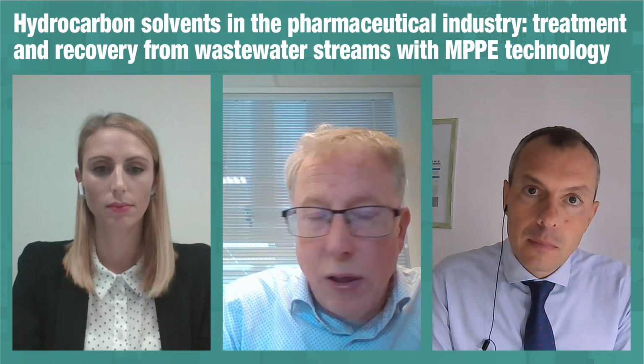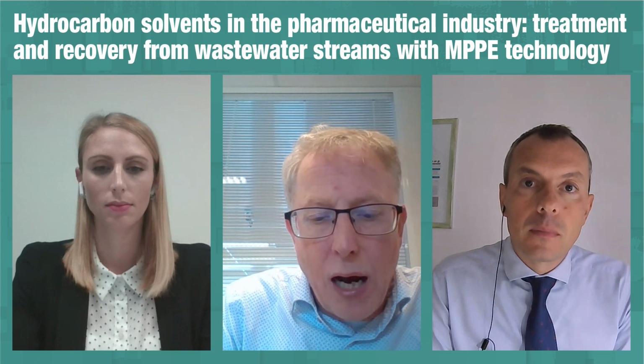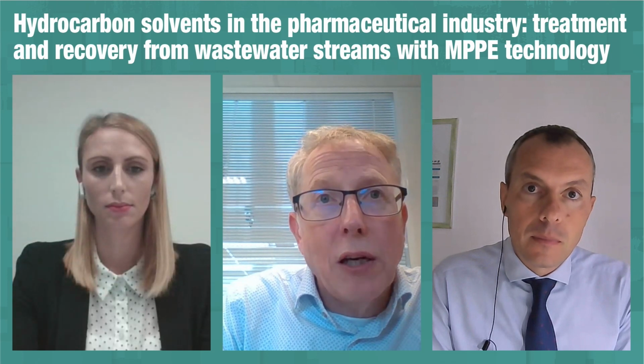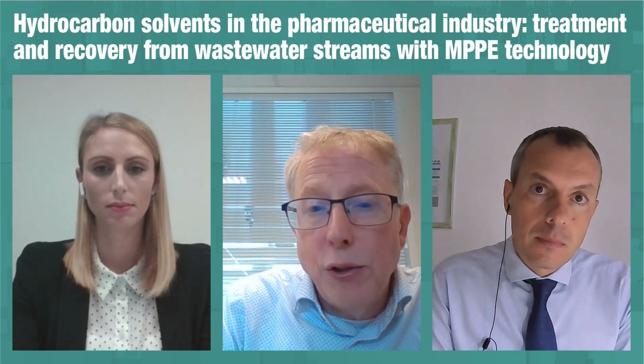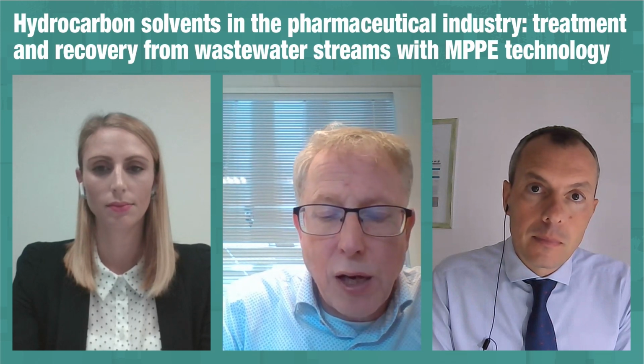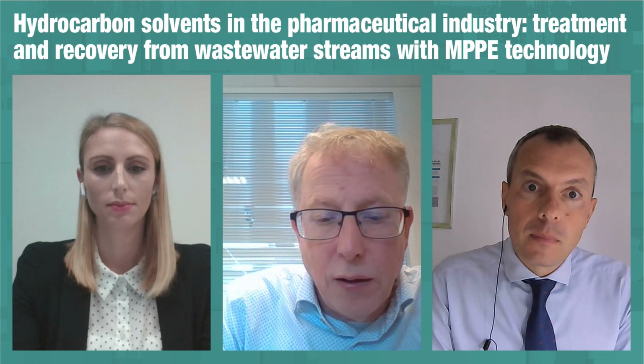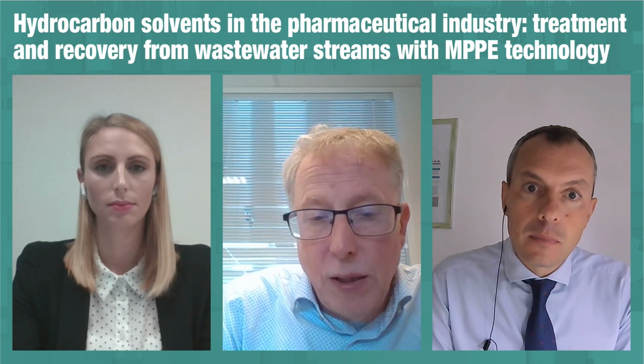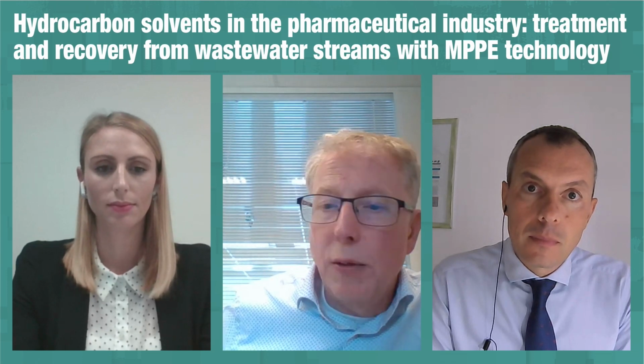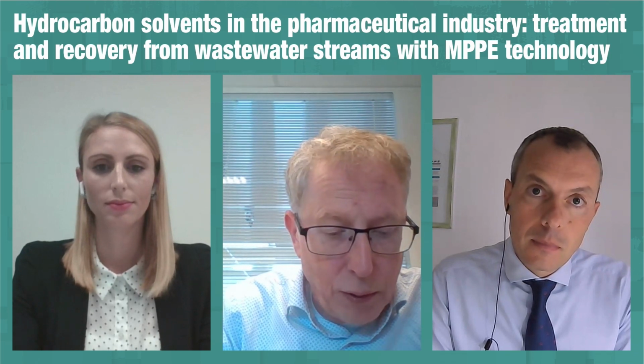And once the media's lifetime has ended, then we take it back and we either dispose of it in an appropriate way, or in some cases, in cases of clean applications, we actually can rejuvenate the media. So we make sure that there's sufficient extraction liquid inside, and that the particles are clean from dust and deposits. And then the media is simply reused. So from that point of view, it's a fairly sustainable way of applying media for wastewater treatment.